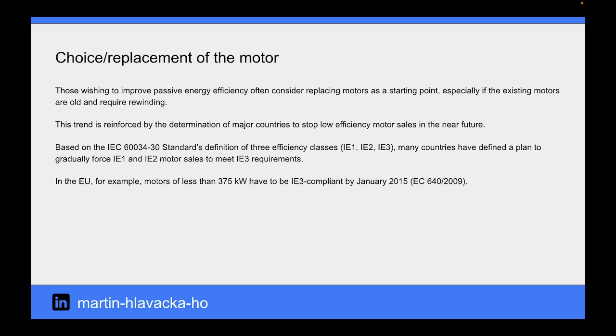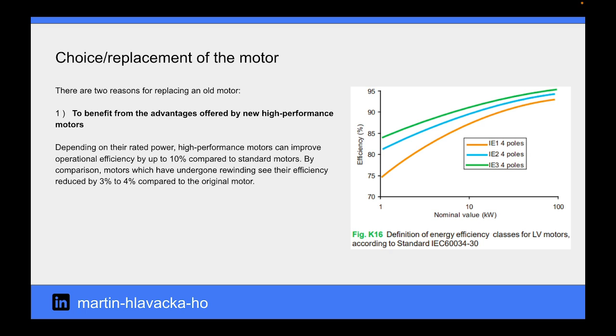There are two reasons for replacing an old motor. The first reason is to benefit from the advantages offered by new high-performance motors. Depending on their rated power, high-performance motors can improve operational efficiency by up to 10% compared to standard motors. By comparison, motors that have undergone rewinding see their efficiency reduced by 3% to 4% compared to the original motor.